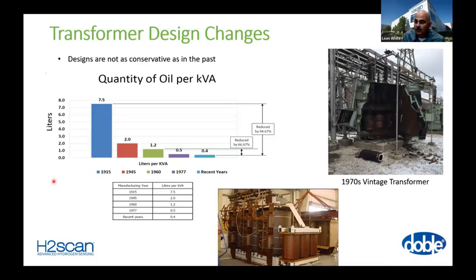So a manufacturing issue that may not have been a problem in the 1950s or 60s can cause a transformer failure very quickly today. And maybe Tony has some data on infant mortality, but my feel is that, I was working with a utility that was replacing their 60-year-old transformers because they were worried that they were going to be failing. And some of the new transformers failed on startup. And so you have to question how long those old transformers would have lasted if they had left them in service.